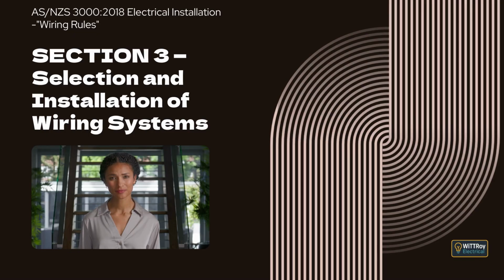Clause 3.10.1.1, Insulated, unsheathed cables. This clause explains that insulated, unsheathed cables must be enclosed in a wiring enclosure along their entire length. The purpose of this requirement is to protect the insulation from damage and to reduce the risk of electric shock or short circuit.